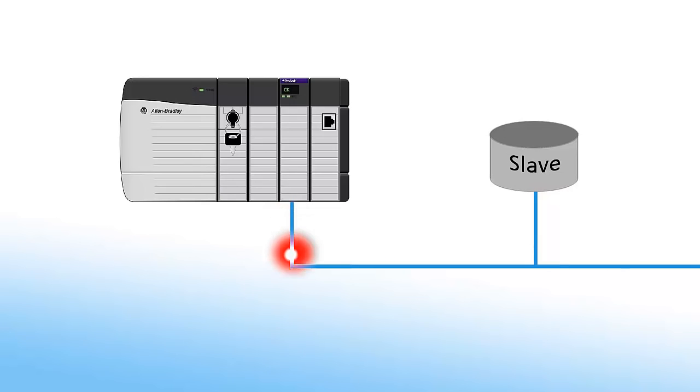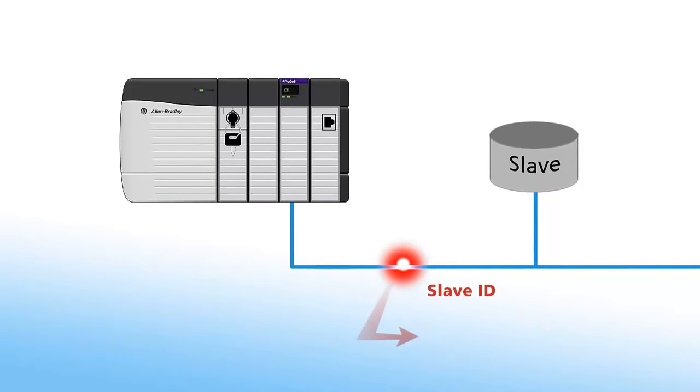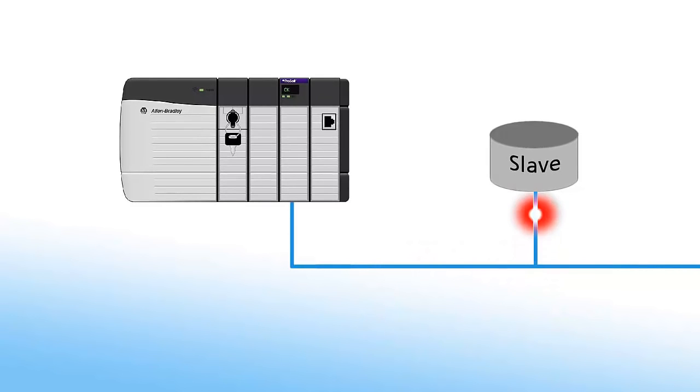To wrap up, we'll take a look at a Modbus RTU message being sent from our master out to a slave device. The message contains the slave ID of the device the command is intended for, the function code to read or write data, and the message data itself. Once the slave receives the command, it will return the requested data to the master in the case of a read command, or it will write the data to its own database and send an echo of the original message back to the master to confirm that the message was received. We hope this video gives you a better understanding of Modbus serial and TCP IP.